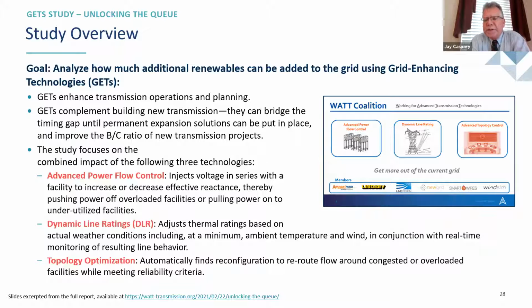This study focused on three technologies. First, advanced power flow controllers, things like smart valves built by Smart Wires, which inject voltage in series to facilities, increasing or decreasing their effective impedance. This allows more power to be pushed through underutilized lines, or decreases flows on overloaded lines by increasing impedance. So we can actually push and pull power on the grid. It's a network, and we need to take advantage of high capacity elements, typically on the high voltage system, which is often a constraint in operations.